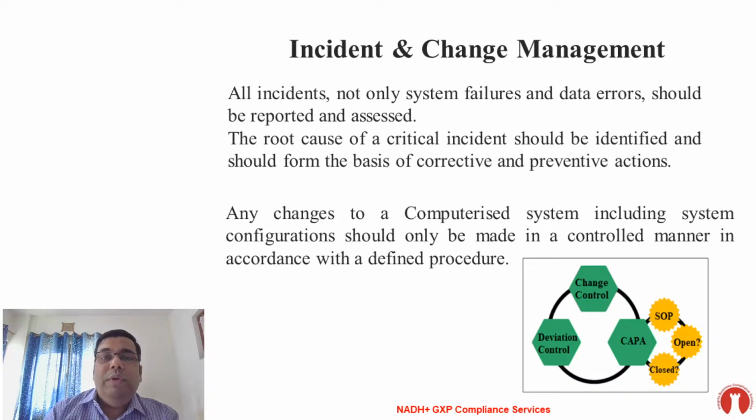But suppose I am making some changes in my hardware, maybe the computer, okay, that also should be recorded. If you don't want to raise a change control, I don't mind, but it should be as per the SOP. At least there should be some format recording what changes I made with respect to the hardware. Maybe some cable connection problem, so I may replace the cable. Maybe some connection port may be the problem, I replace that.